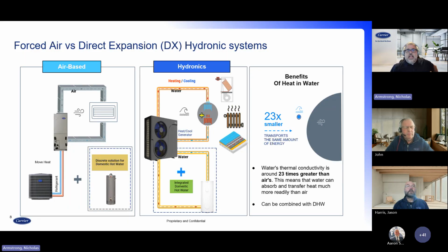This slide here is going to highlight really the fundamental difference between an air-based system and the hydronic system that we're talking about here, often using the direct expansion or DX cooling for modern home hydronic systems. The air-based systems typically rely on just refrigerant to move heat directly into the coils. And then with the hydronic system here, you see that we're using the water as the heat transfer medium, if you would. And the benefit to that is water is much more thermally conductive than air. So we're utilizing that thermal conductivity to absorb that heat and move that efficiently.